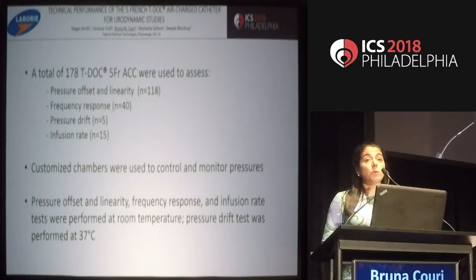As you can see in figure A, we are showing a linearity of 0.99 with a standard deviation of 0.01 with an R-squared of 1. Offset was negative 0.18 plus minus 1.09% at 136 centimeters of water, and minus 1.65 plus or minus 0.65% at 272 centimeters of water.